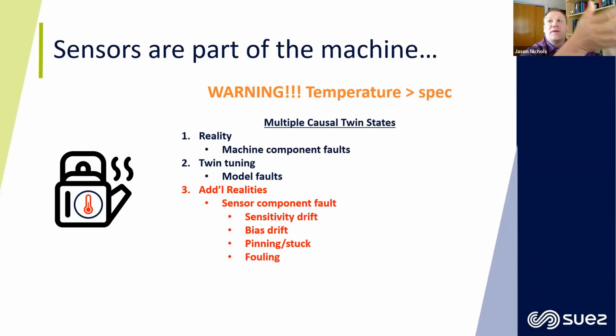It's very simple, and now in many cases automated, to detect those types of model errors. But there are additional realities in the state space when you're in the real world that might not be considered when the twin was made. These are things like sensitivity drift. Sensors fail and foul over time on slow degrade curves, so it's hard to detect them as they drift slowly away from the sensitivity they had at the manufacturer.